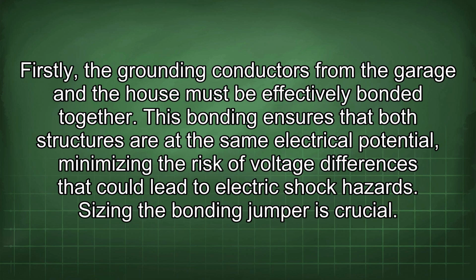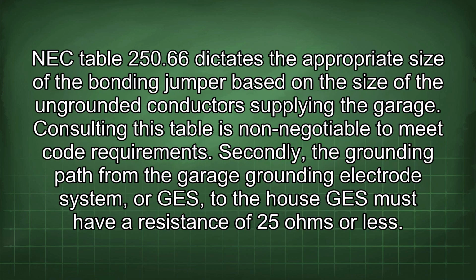Sizing the bonding jumper is crucial. NEC Table 250.66 dictates the appropriate size of the bonding jumper based on the size of the ungrounded conductors supplying the garage. Consulting this table is non-negotiable to meet code requirements.